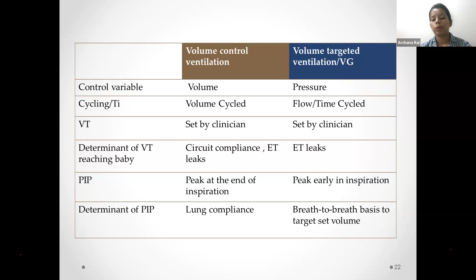As we have just discussed, in volume control ventilation the PIP peaks at the end of inspiration, and in volume target ventilation, as it is a pressure mode, the peak is usually early in inspiration. In volume control, the PIP is determined basically based on the lung compliance. The better the compliance, the lower the PIP will be. It will be adjusted by the ventilator. And in volume target ventilation, the ventilator will sense each breath, either the previous breath or the same breath, and assess whether it is sufficient to deliver the set tidal volume or not, and then in the subsequent breaths it will make adjustments.